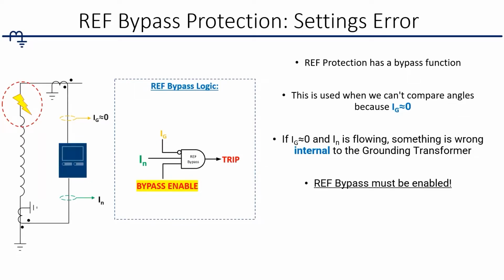So an REF system, when you go test restricted earth fault protection, every REF system has a bypass. It's there for a reason. It's there for this exact reason, to be specific. When it can't compare current angles, like for example when you're in a microgrid and the utility is not present, like we showed in the previous slide, and an internal fault happens, there is no angle to compare to. So SEL and other manufacturers have made something called REF bypass logic.